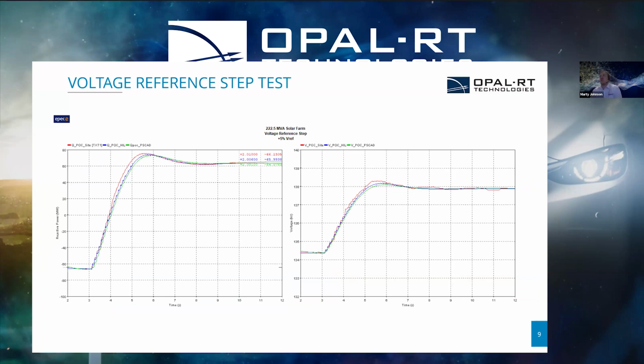What we can see here is a particular test that we perform, called a voltage reference step test. This is where we aim to change the voltage at the point of connection, and we do a 5% step. I have 3 signals plotted here. The green one is the PSCAD model, which we have to develop as part of our compliance for our R1 package, before we get our connection assessment and before we do the commissioning of the site. So that's what theoretically the plant should do.